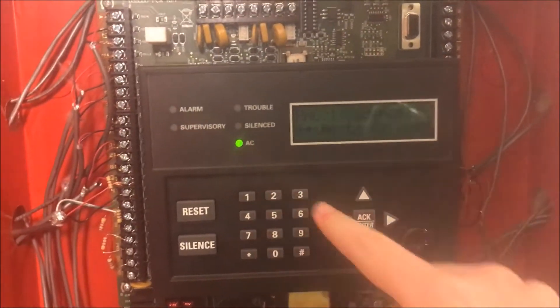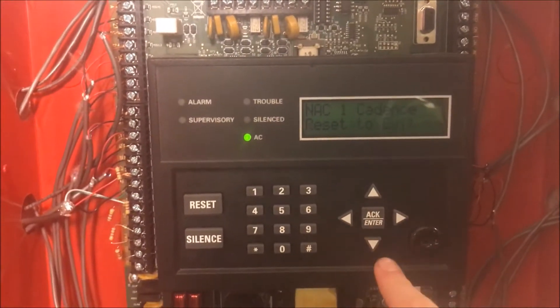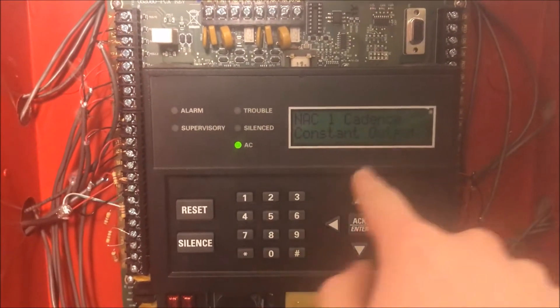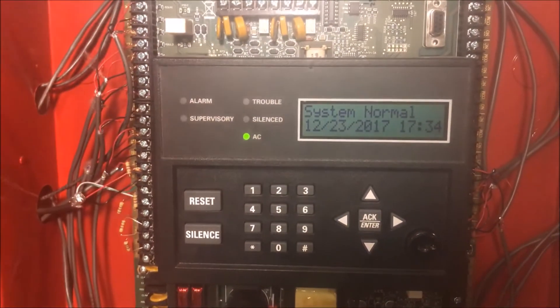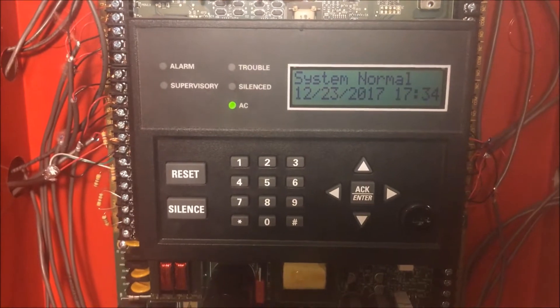So here is what happens — I will show you. The NAC1 cadence is set to constant output, which means it is just flat out straight power, no coding, no anything. So now that the system is normal, I am going to open up a pull station and send the system into alarm. Watch.